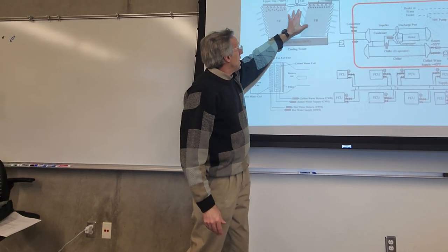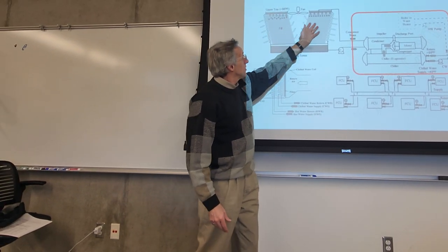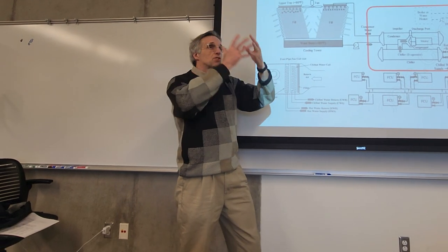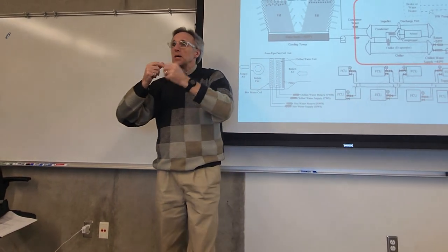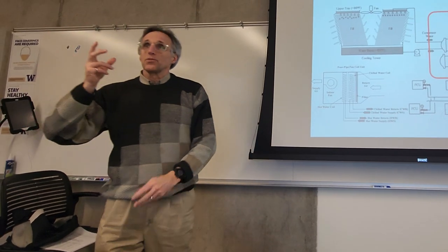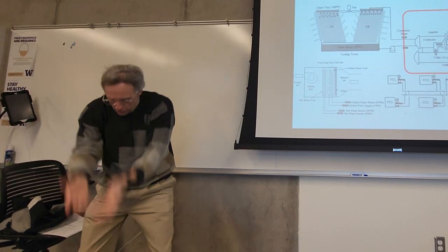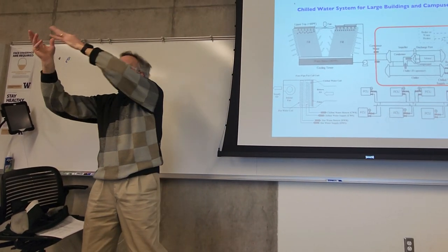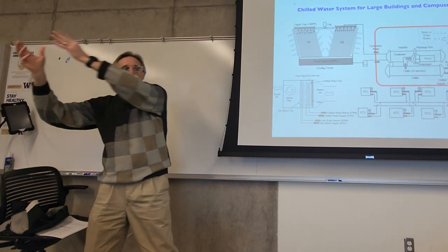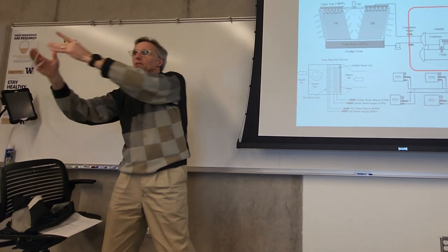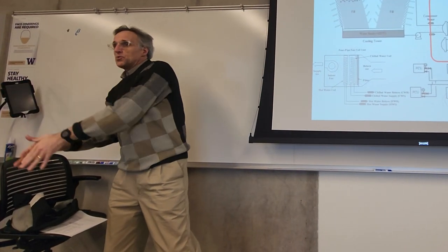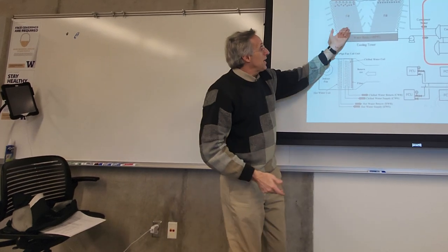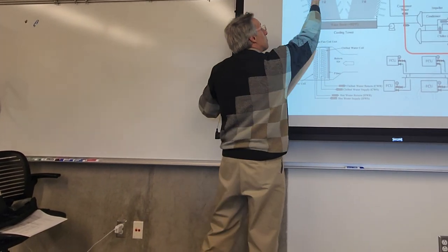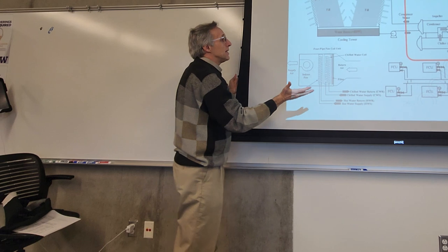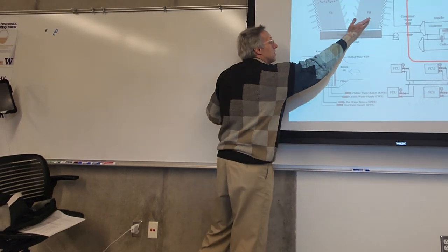As that hot water trickles down, this actually has fill in it. It's stuffed with packing material, like little weird shaped things. So when the water comes down, it can't just fall straight down. It actually has to trickle down all these little passages. So it takes a long time and it contacts a lot of surface area as it comes down. And while it's making its way down, air is going up. So that air is picking up the heat.